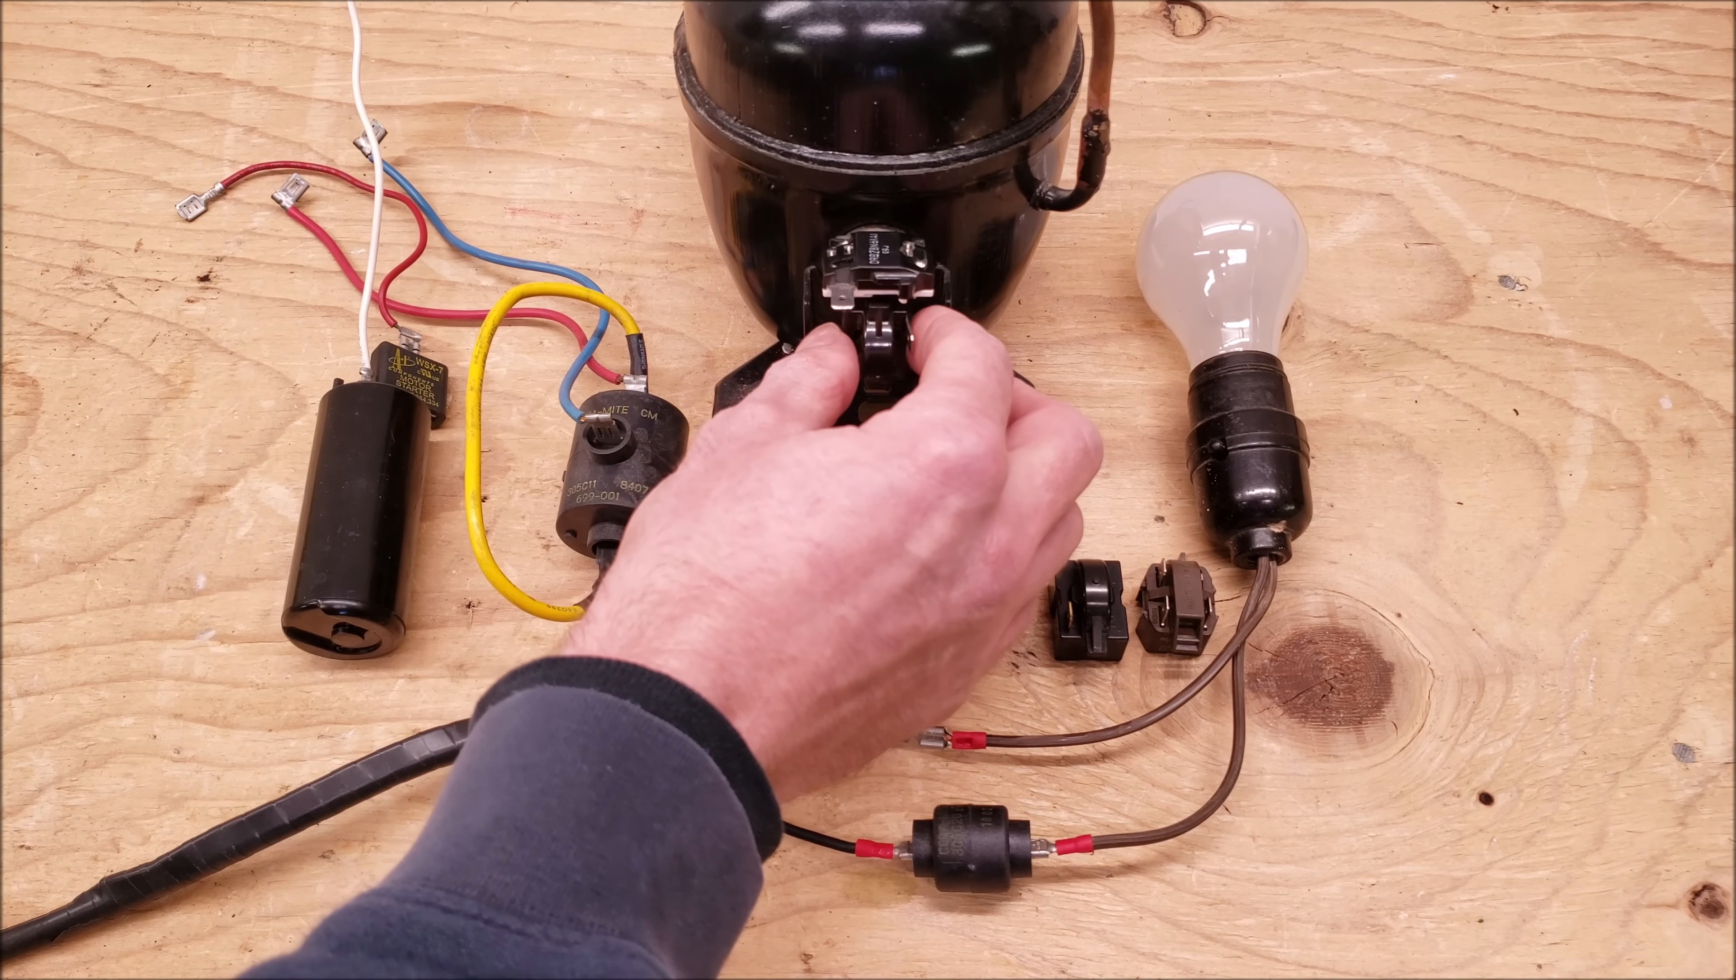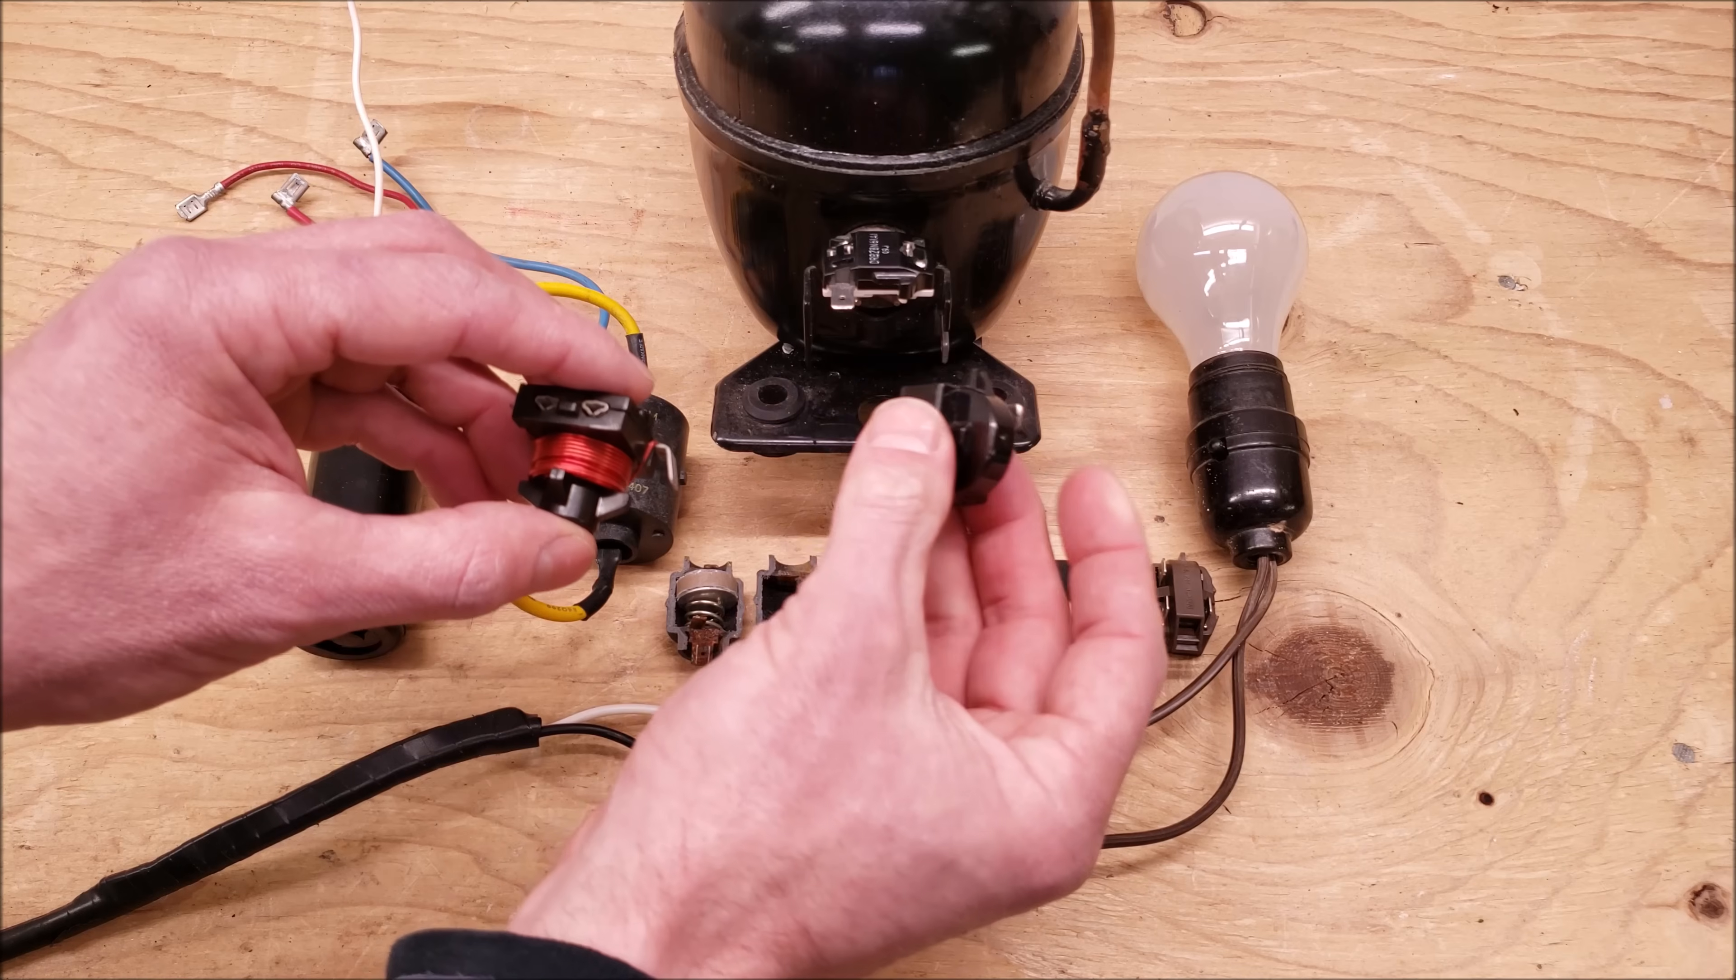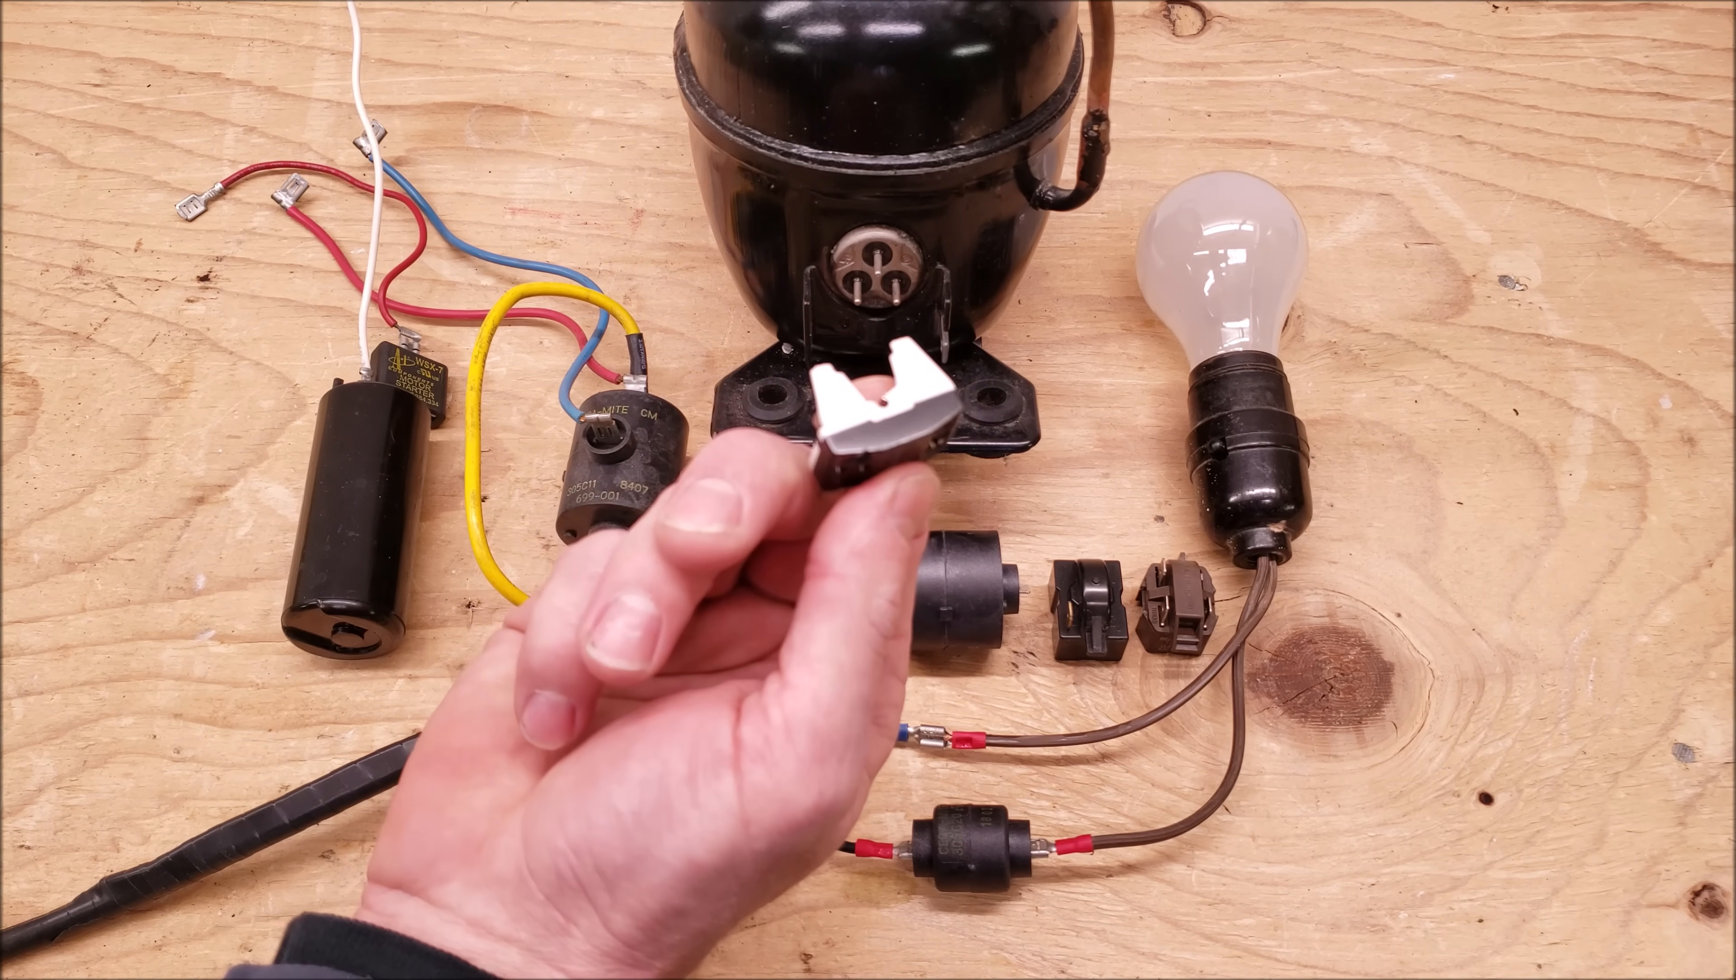So the PTC thermistor right here is getting connected directly to the start and the run terminals. And you don't want to get that confused with this right here. This is a current starting relay and you can tell the difference between a PTC thermistor and a current starting relay due to the wire coil on the outside. And this right here, this is just a compressor protector and it has a little thermo disk inside. So this is attached to the common terminal.